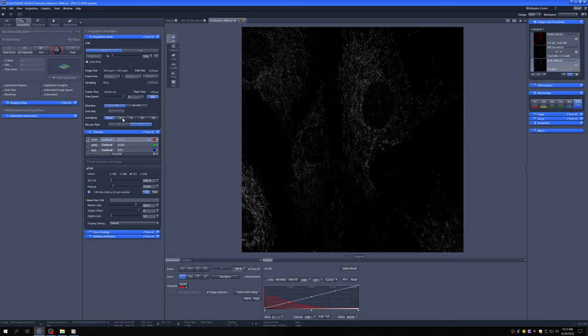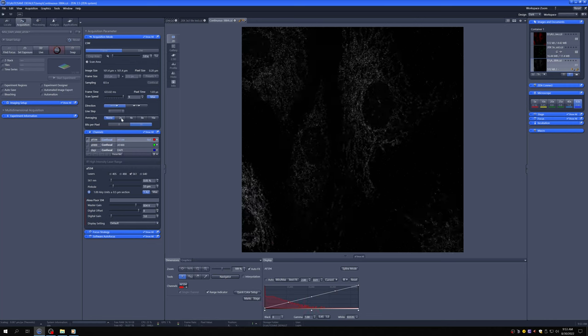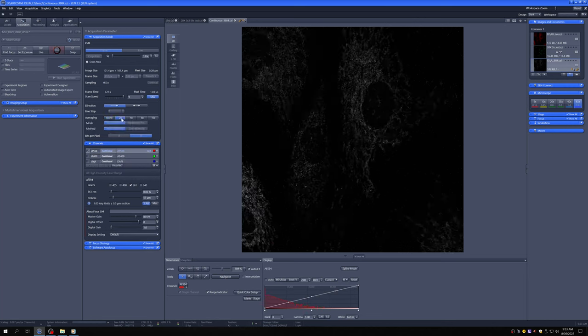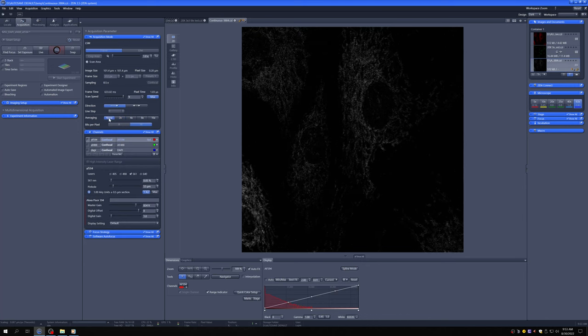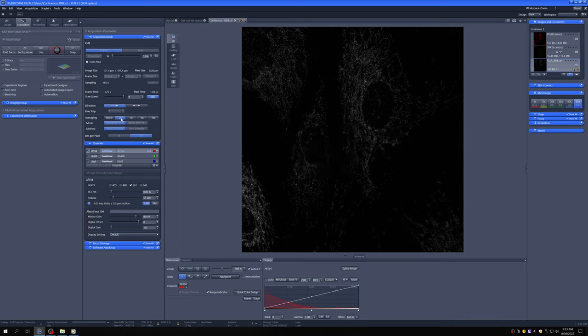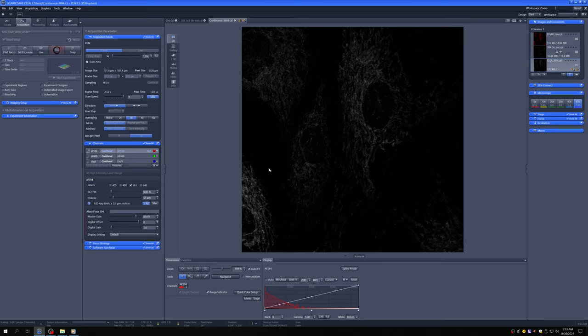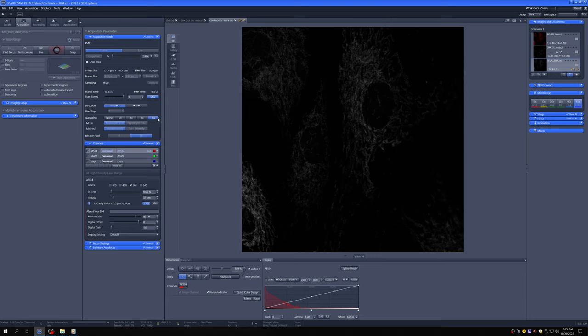If I go to 2x averaging, I expect the frame time to double and I expect the quality to improve. You can see there's the improvement in quality, very clear from none to 2x. If I go to 4x, you can see that it takes even longer. You can actually see it sweeping and the quality improves even further. If I go to 8x, there's a more subtle change in quality. And if I go to 16x, it's really slow and you can see just a very subtle increase in quality.